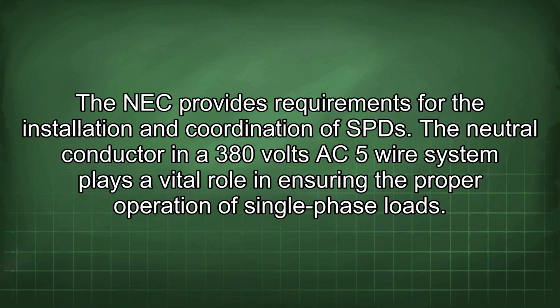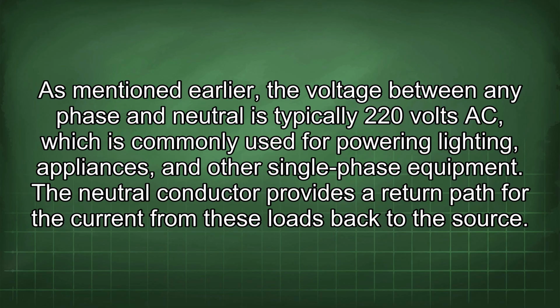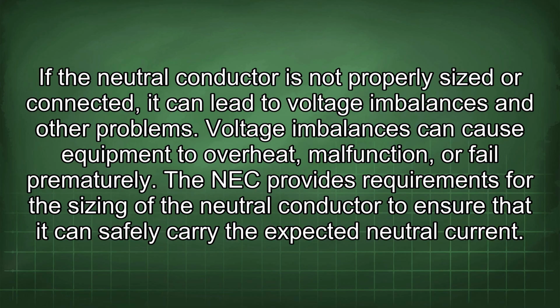The neutral conductor in a 380 volts AC 5-wire system plays a vital role in ensuring the proper operation of single-phase loads. As mentioned earlier, the voltage between any phase and neutral is typically 220 volts AC, which is commonly used for powering lighting, appliances, and other single-phase equipment. The neutral conductor provides a return path for the current from these loads back to the source. If the neutral conductor is not properly sized or connected, it can lead to voltage imbalances and other problems. Voltage imbalances can cause equipment to overheat, malfunction, or fail prematurely.